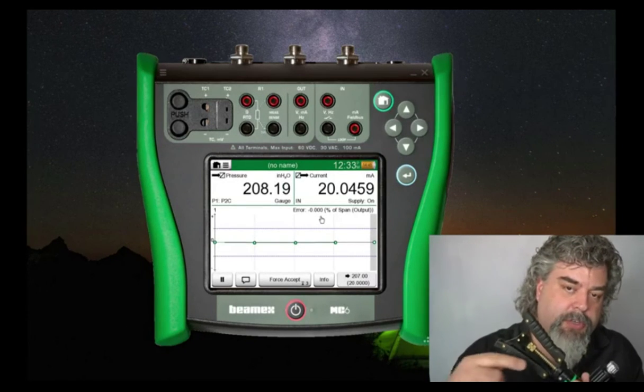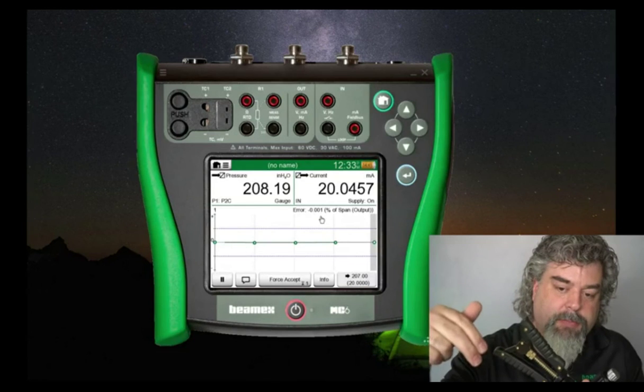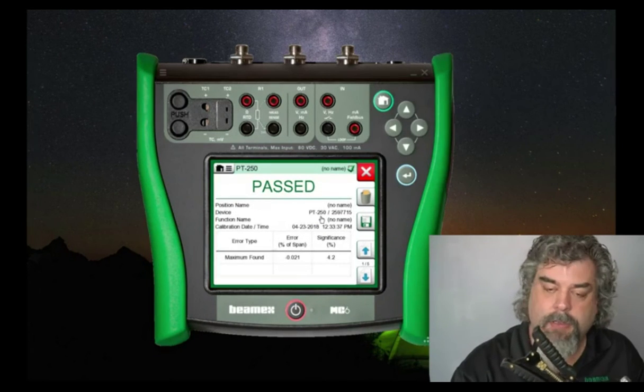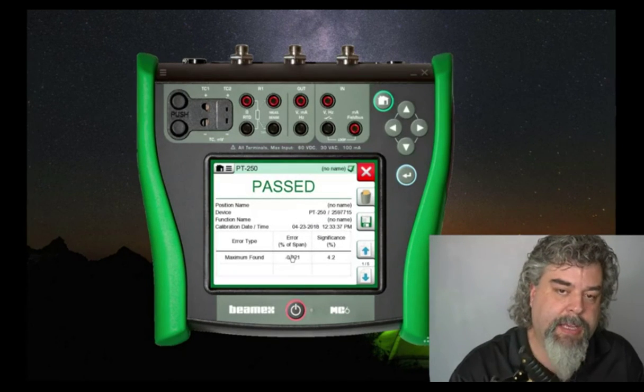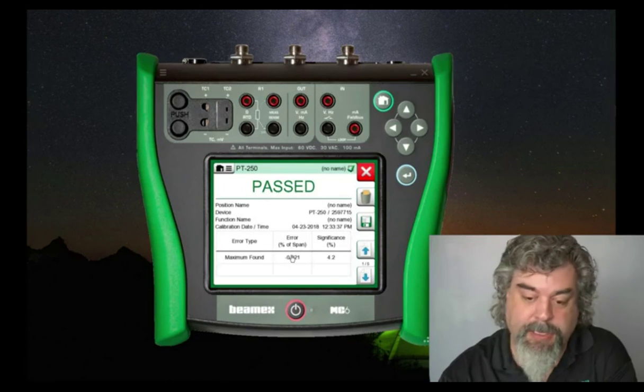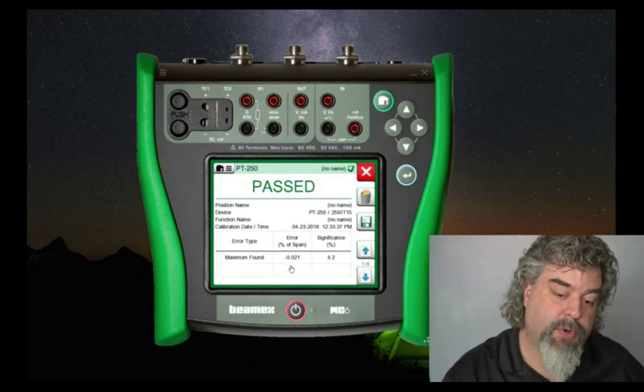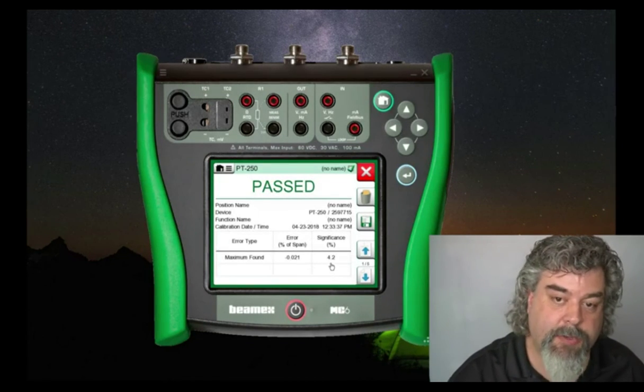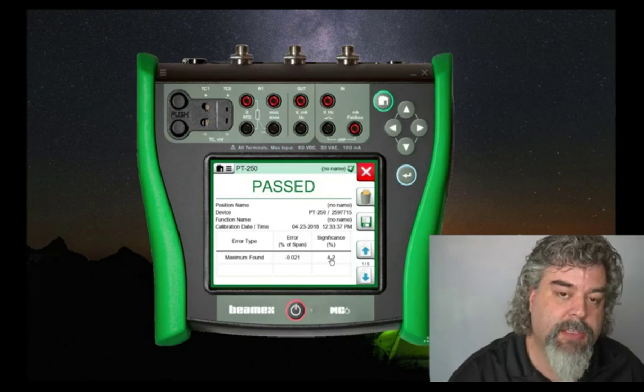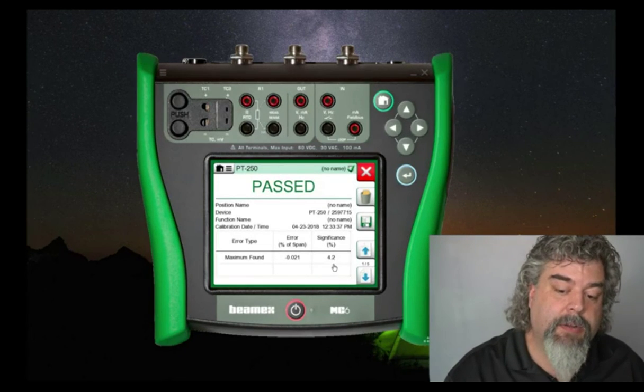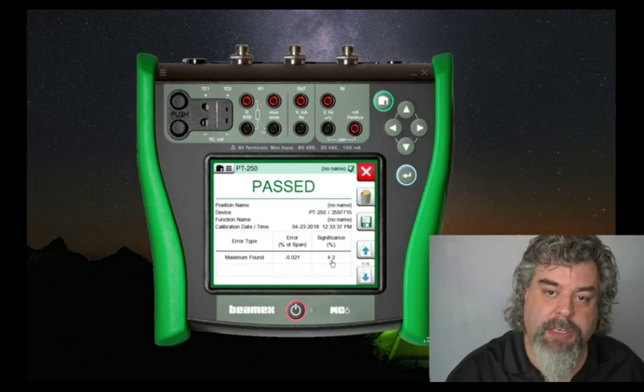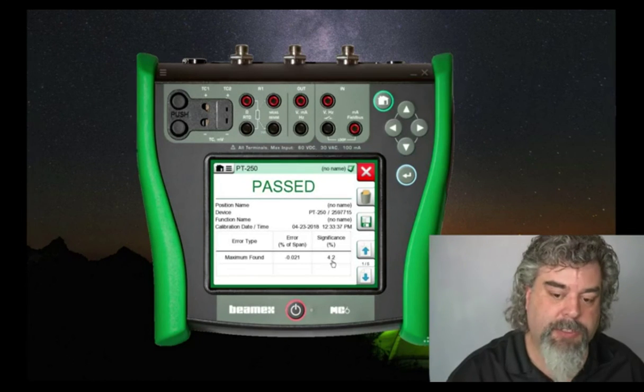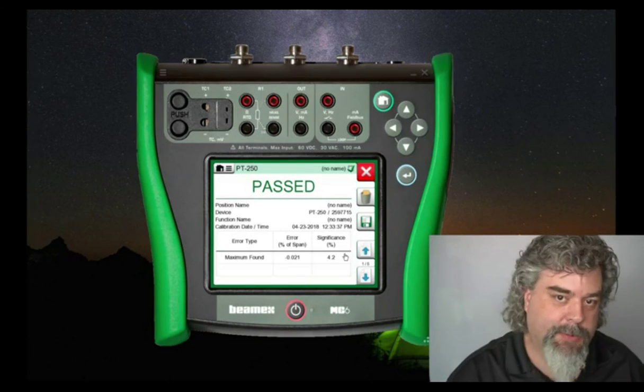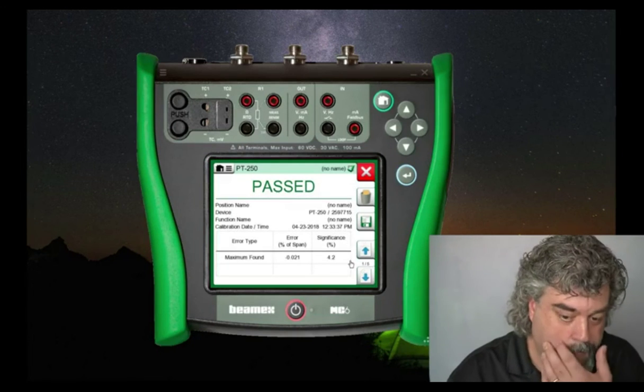Now I'm resisting the urge to bring down the fine tuning because wherever we are in the number, so this one passed, our actual error when we set the pump down is 0.021% of span in a negative direction. The significance means that this error equates to 4.2% of our error tolerance allowed. And our error tolerance allowed was 0.5% of span.